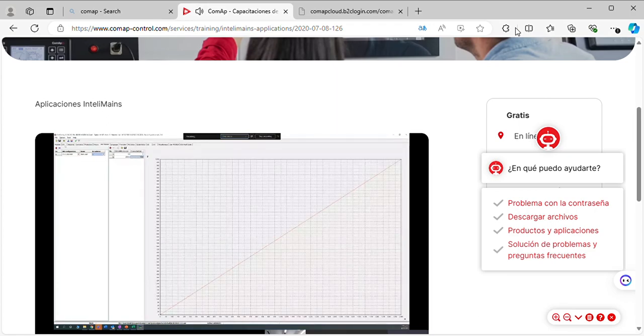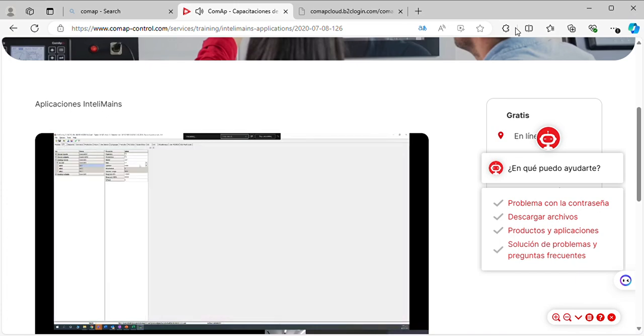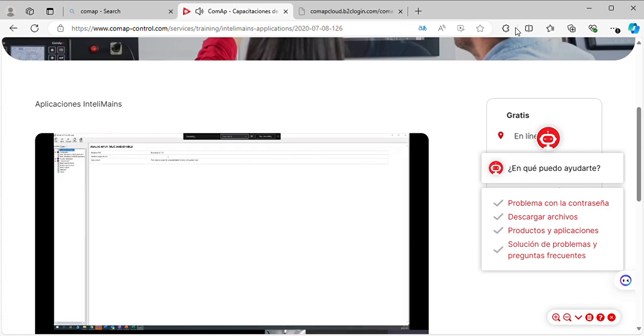I go back to my IO, I choose this, and I can choose my sensor. If you scroll down, you will find something called base load, the one which we prepared. And we have set the dimension to kilowatt. When it comes to function, you can see here, external base load control. And if you are not sure of that function, again, you have the choice to click function F1. This input is used for external determination of system base load.